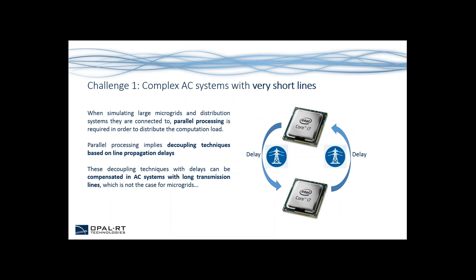The first challenge related to power systems is the fact that there are complex AC systems with very short lines that need to be simulated in real-time. When simulating large microgrids and distribution systems, parallel processing is required to distribute the computation load. Parallel processing necessarily implies using decoupling techniques based on line propagation delays, but long transmission lines — which compensate these delays — are typically not available in microgrids.